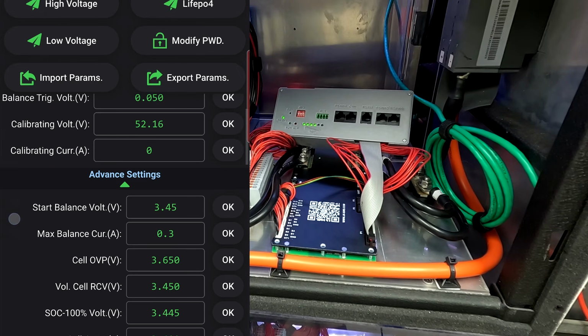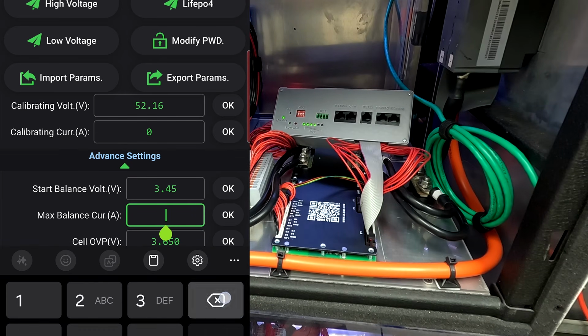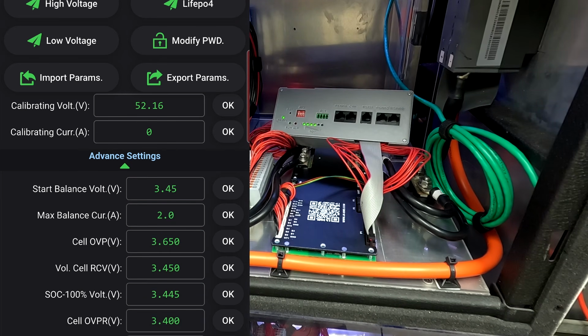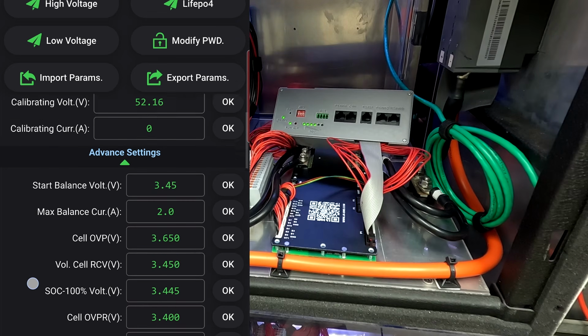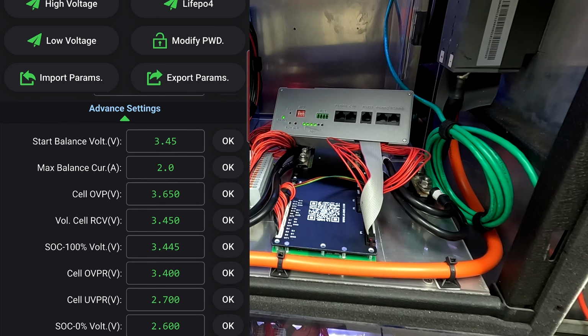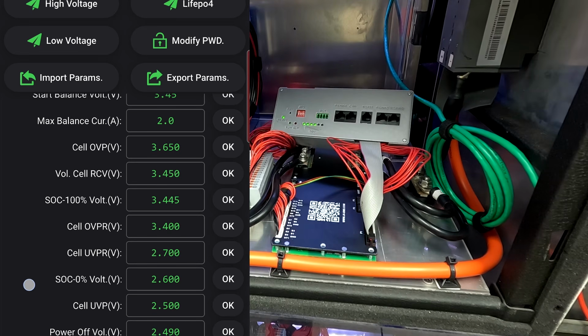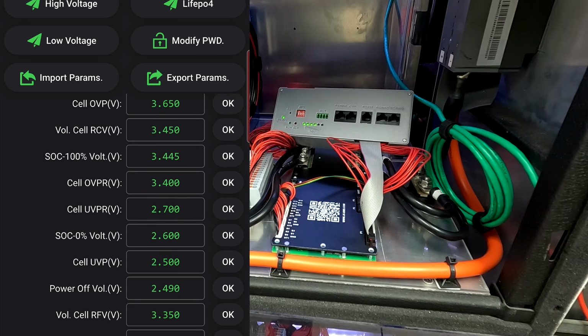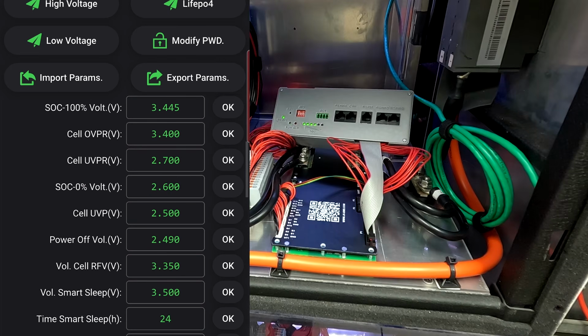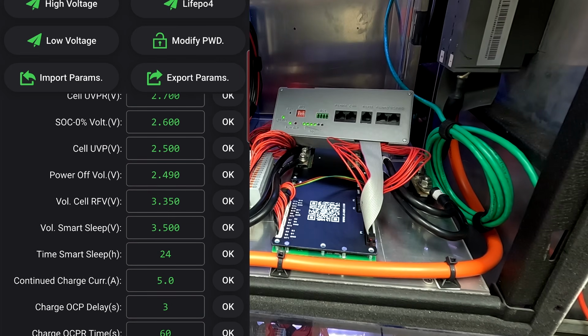That's good. So start balance 3.45, maximum balance current could be 2 amps for these larger cells, 3.65, RCV 3.45, 100% reset, 3.445 which is 55.12. The overvoltage recovery, that's fine. Undervoltage protection, cell undervoltage protection 2.5, power off at 2.49. Requested float voltage 3.35, which is 53.6 volts.